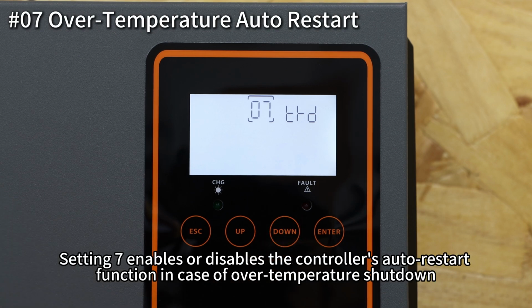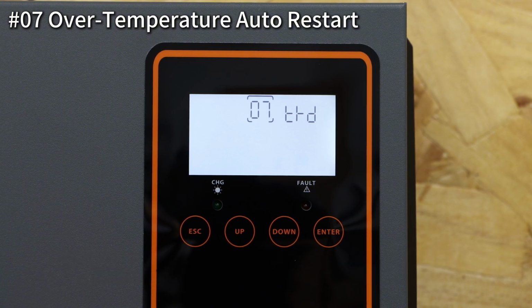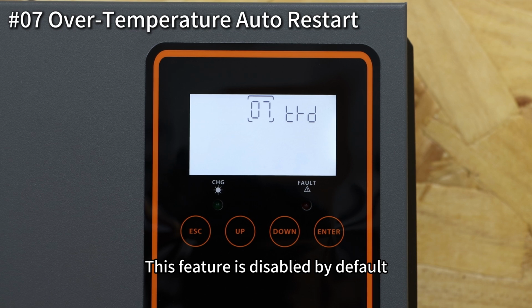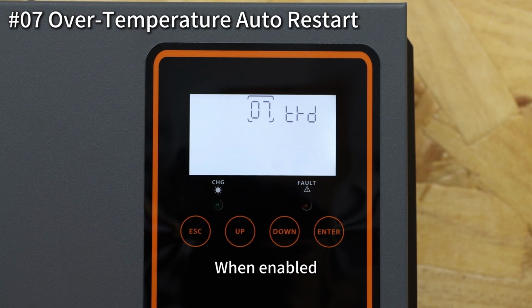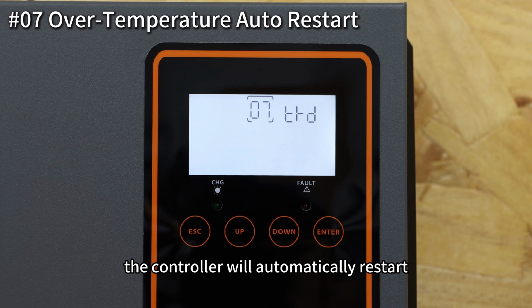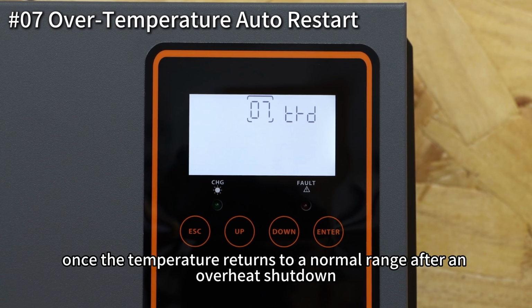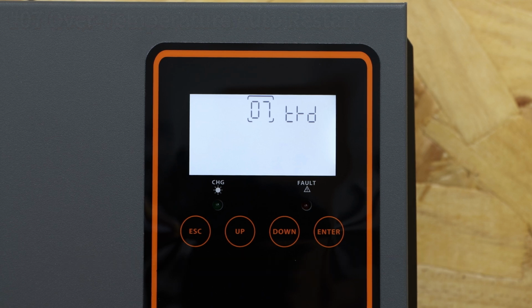Setting 7 enables or disables the controller's auto-restart function in case of over-temperature shutdown. This feature is disabled by default. When enabled, the controller will automatically restart once the temperature returns to the normal range after an overheat shutdown.